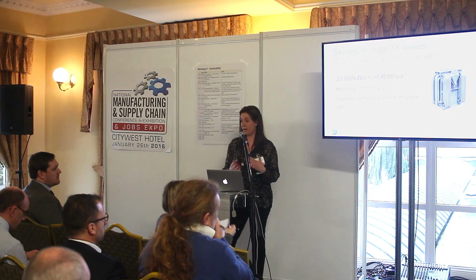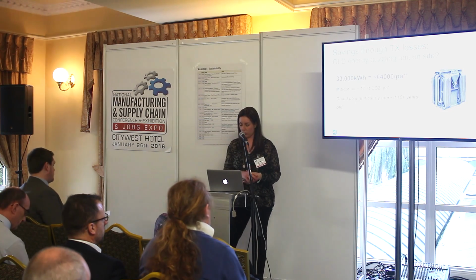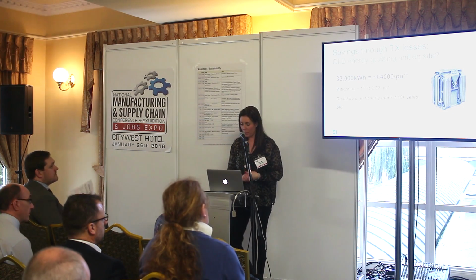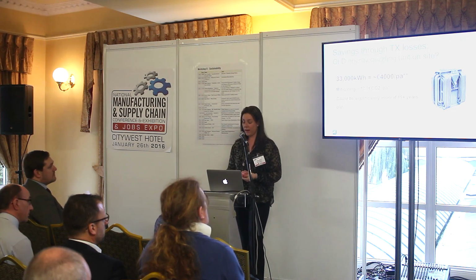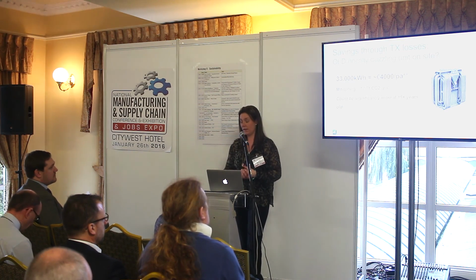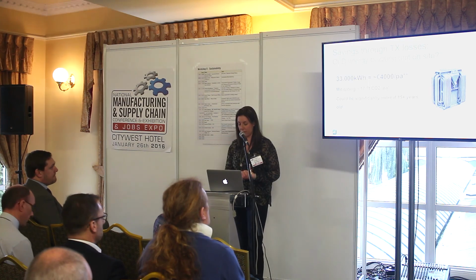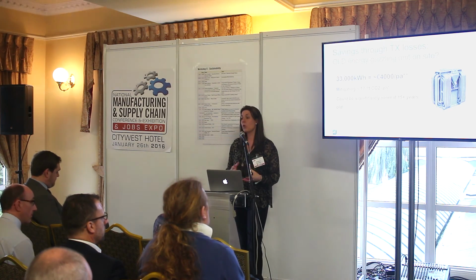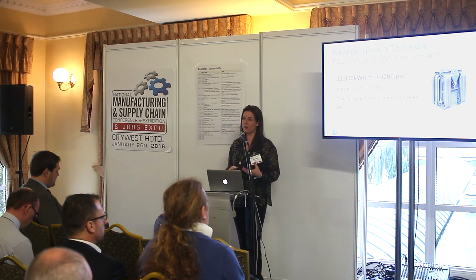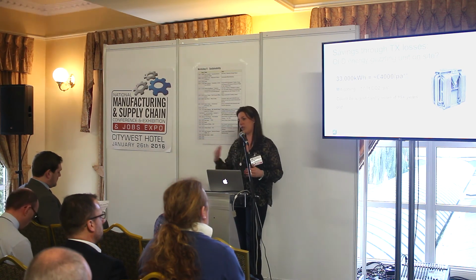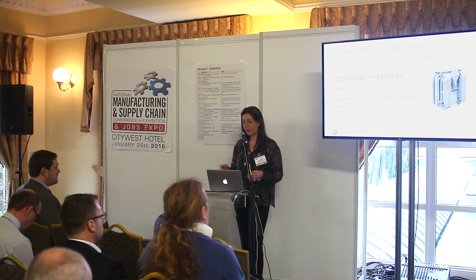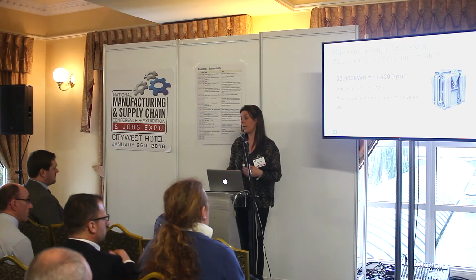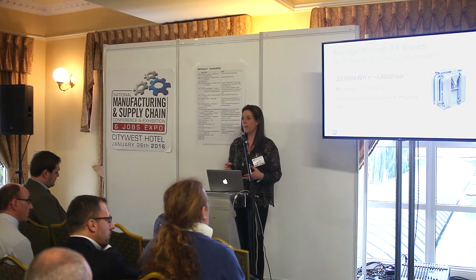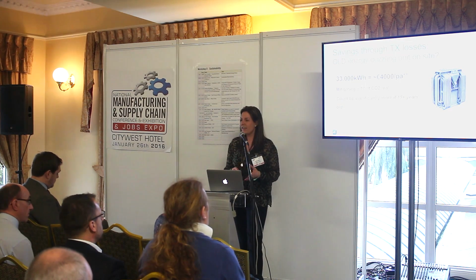If you had an existing installation with this transformer - I quite like this transformer, but I'm a bit sad because it's my job - anyway, this transformer is old, probably 50 years or so. If you have one of those at your site, think about fast-tracking its replacement, because you may have looked after the transformer and the oil may be in good condition, but the efficiency isn't so good.